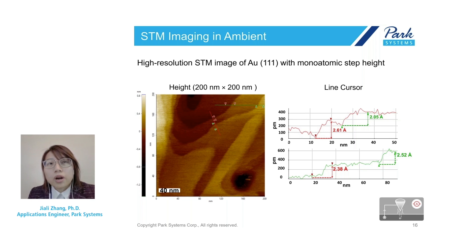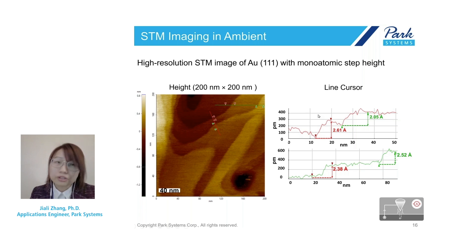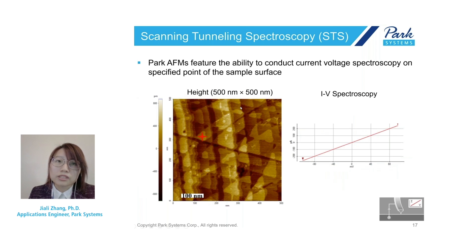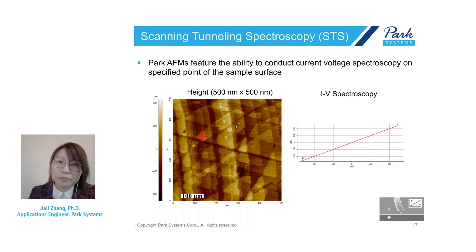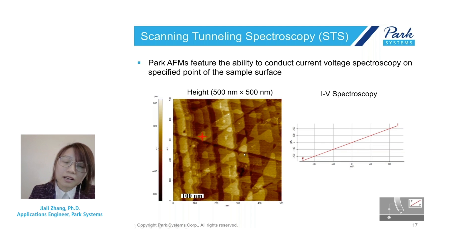Not only does our STM module enable users to obtain high-quality images, but using the STM tip as a nanometer-scale contact, you can also generate scanning tunneling spectroscopy, or STS, results. This STS result provides a plot of current as a function of bias, measured at a selected point after taking an STM image. It can be used to study the local electronic state of the sample at designated positions.